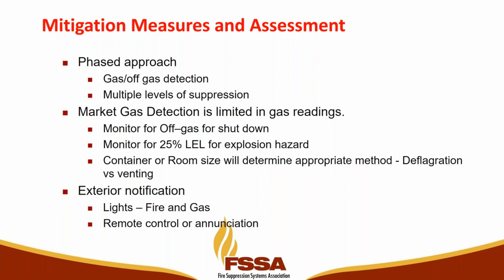Another question: is there a benefit to shutting off the charging circuit as soon as detection occurred? Absolutely. If you can take it off load from that off gas, which is charge or discharge, you run a very good possibility of stopping it from going into thermal runaway. But that time frame can be short. As I said, it could be seconds, it could be minutes. Depending upon the failure mode, you may have as many as 15 minutes, but you absolutely want to take it off charging as quickly as you can.